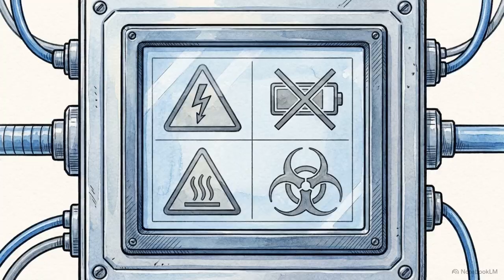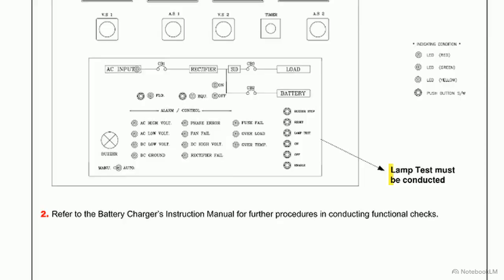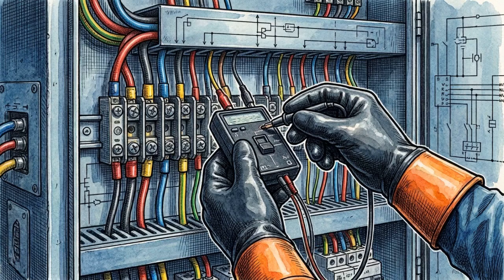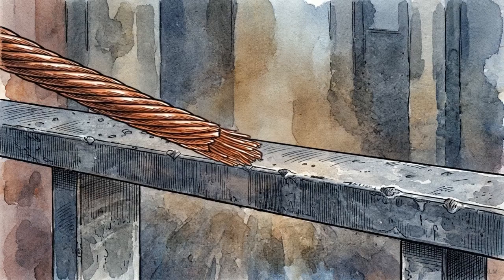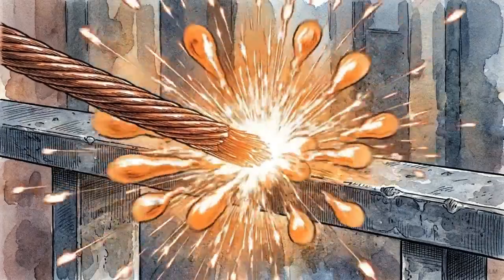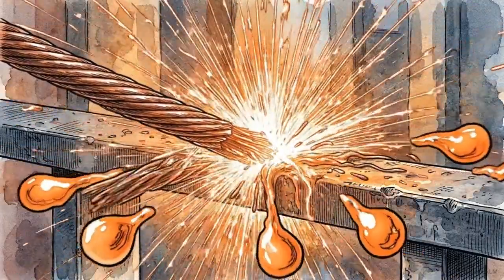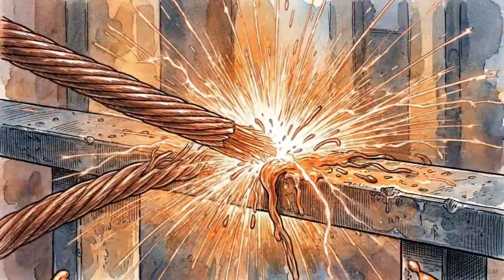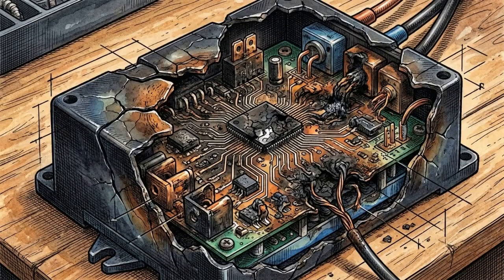As shown on this panel schematic, the first step is executing a simple lamp test to confirm all visual LED indicators are physically operational. From there, technicians use specialized high-impedance simulation links to safely induce positive and negative ground faults. There is a strict operational warning here. You must never create a dead permanent ground fault on a live DC system during simulation. It creates an immediate arc hazard and can severely damage the relays.